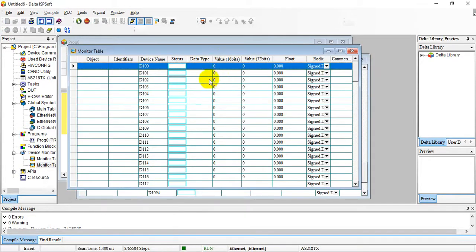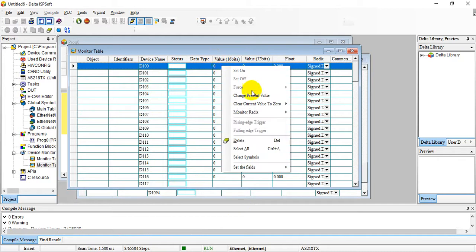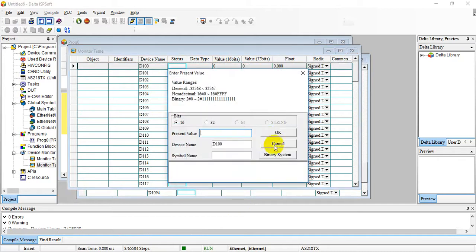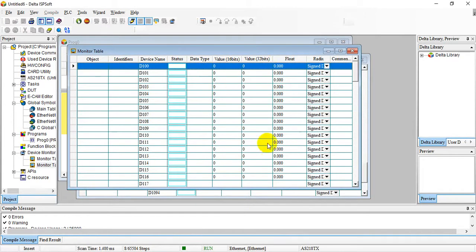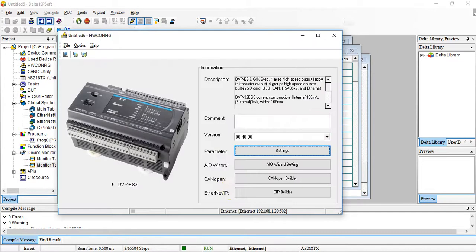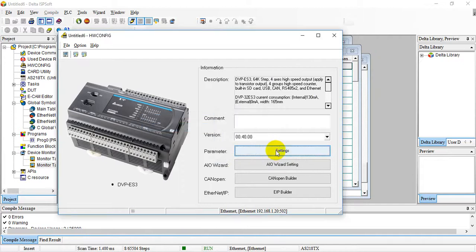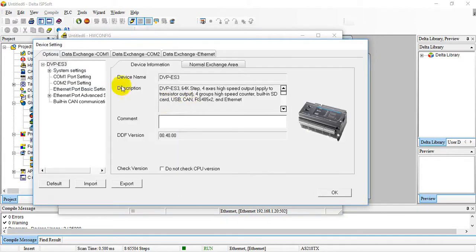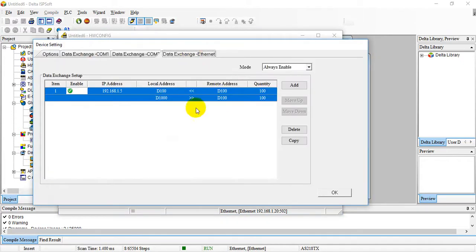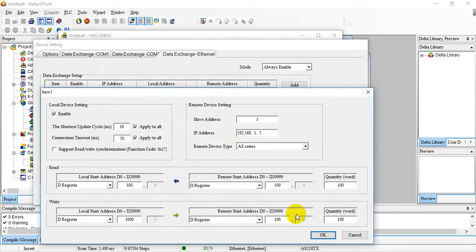Here you may find when we try to write the value, it all becomes zero. Maybe we did some wrong settings, so let's go back here and check the settings again. Let's go over here and check. Oh, you can find here we did a wrong setting. The read and write are assigned to the same address, so now we change it to 1000.